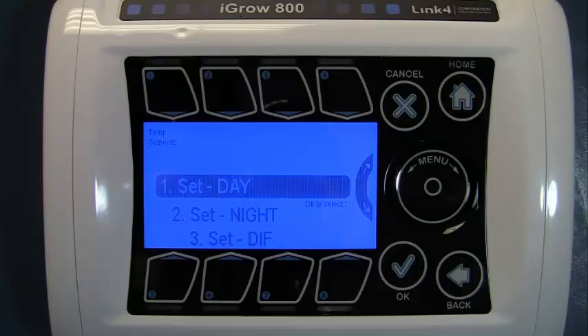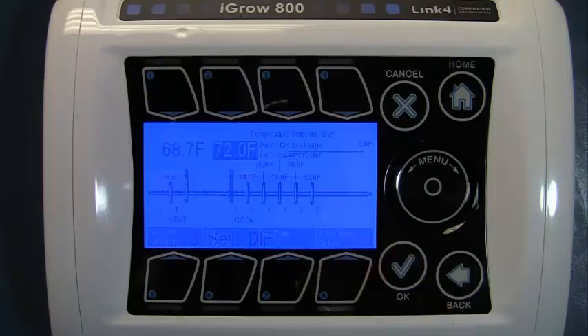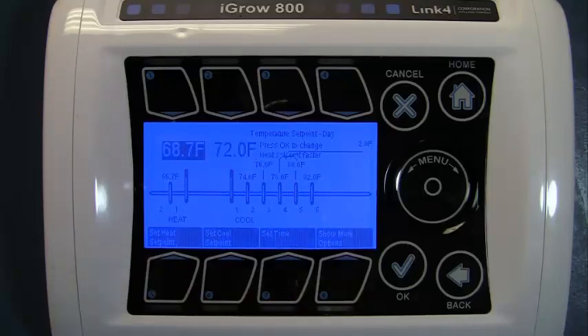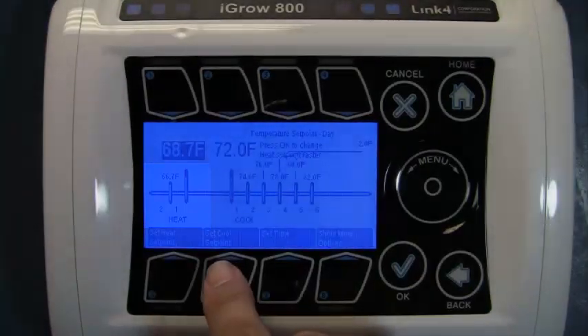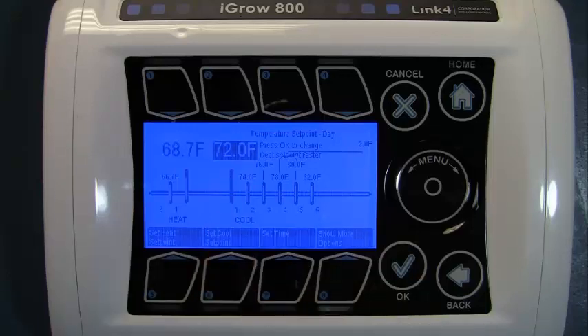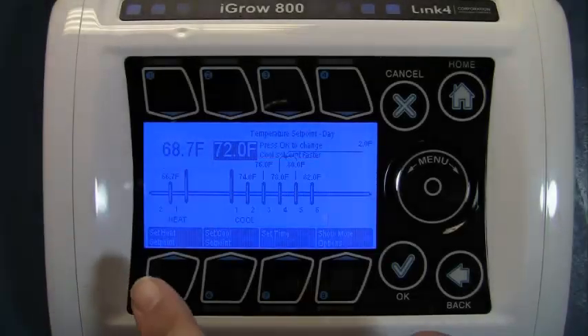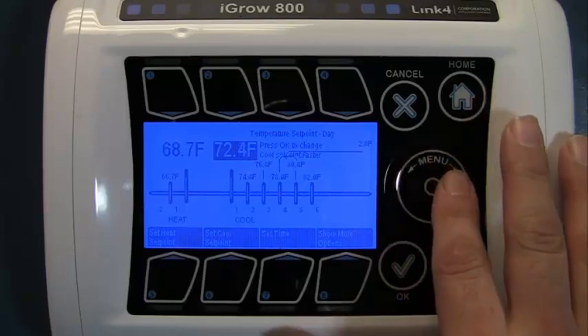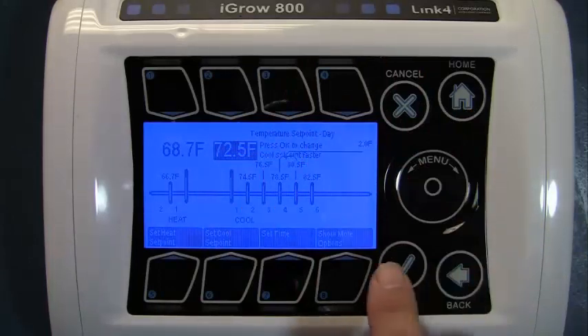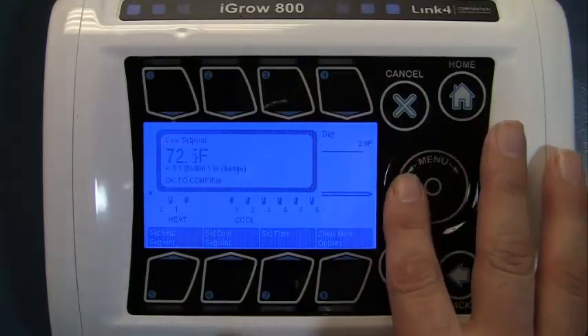First we're going to look into day and press OK. This brings you to the basic set point menu system. By pressing button number five, it highlights the heat set point. The heat set point is the low temperature target at which the heat stages are engaged. Pressing button six brings up the cool set point, which is the high temperature target at which the cool stages are engaged. A user can change the temp by using the wheel — simply rotating it gently, or you can highlight and press OK and rotate the wheel as well.